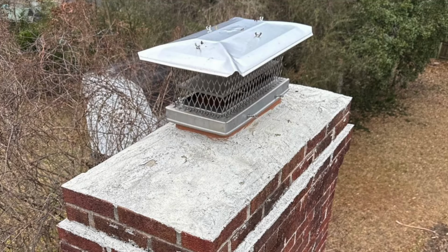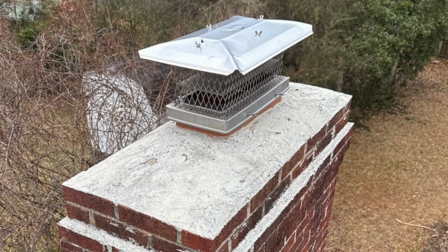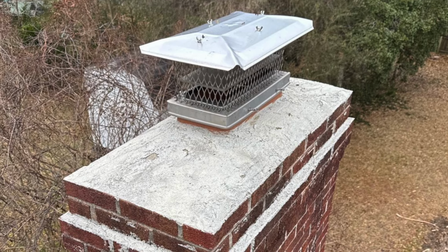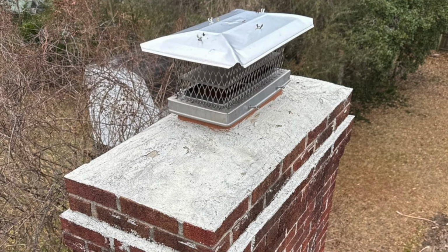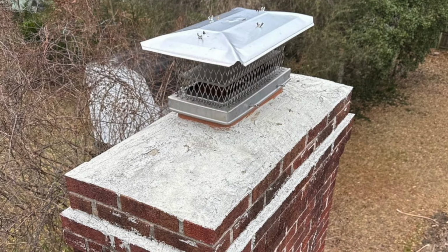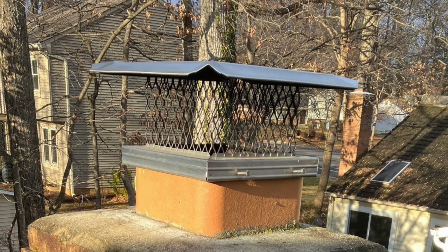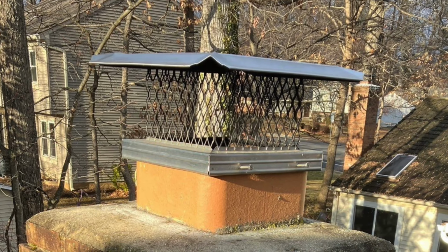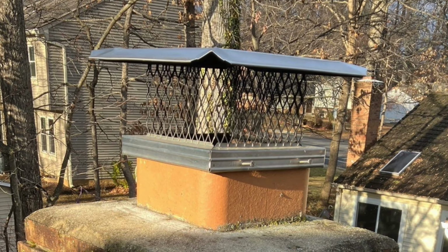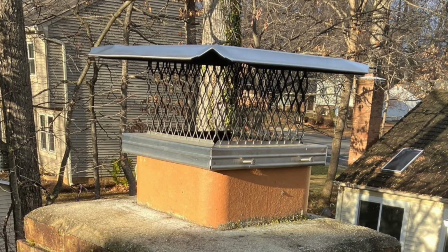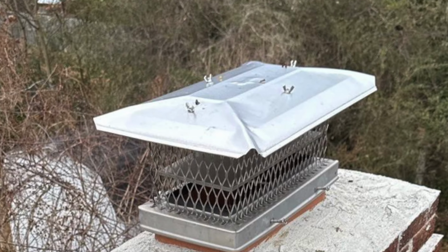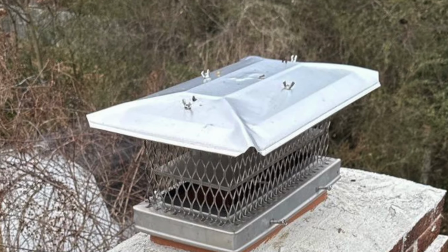Chimney caps and spark arresters play an essential role in protecting the flue system from moisture, wildlife, and embers, but they must meet specific listing and performance requirements to be considered safe and code compliant. One fundamental rule is that the net free area of the cap or spark arrestor must be at least 4 times greater than the cross-sectional area of the flue it serves.